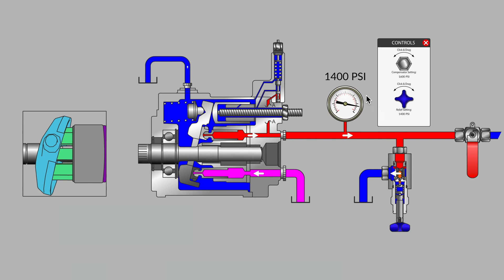If I tell you that the machine manual says that our hydraulic system pressure should be set no higher than 1100 psi, then that is another way for us to know that the system is currently maladjusted.